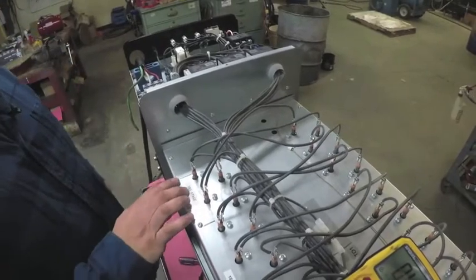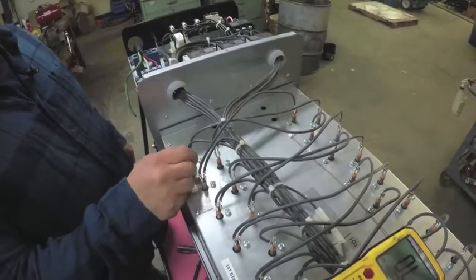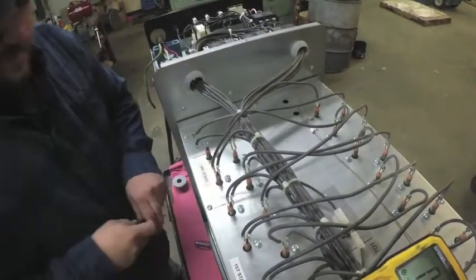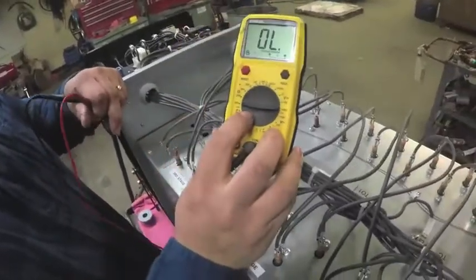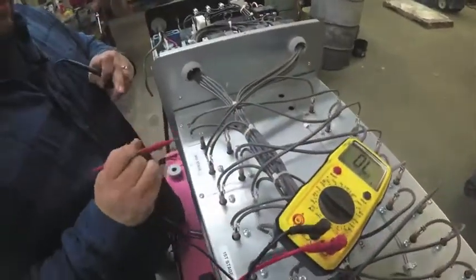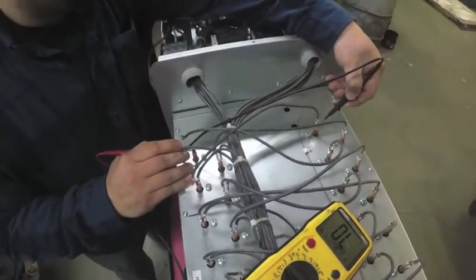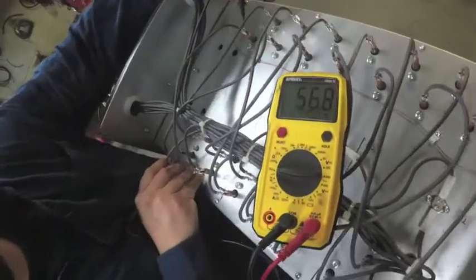Next, we're going to be ohming one of the coils. You need to remove one side of the coil off from the male prongs. Turn your voltmeter to ohms. Take one end on one side, one end on the other. As we can see, we have 56.8 ohms.